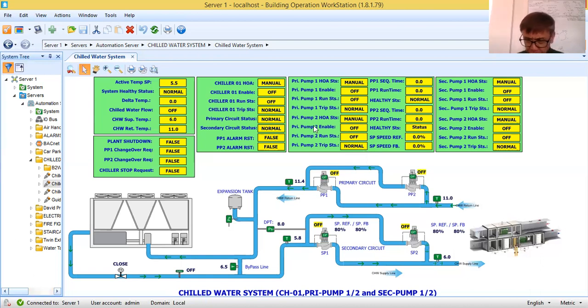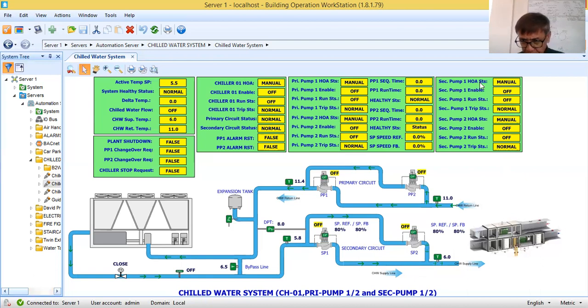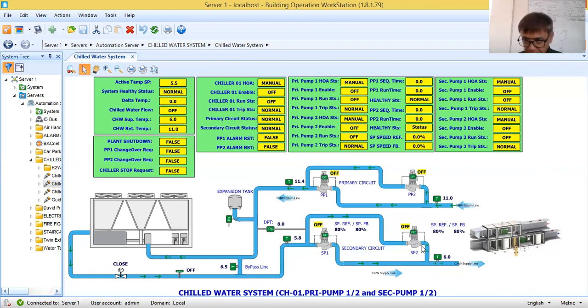The control point is the pump enable and disable command. Likewise, the other component in this chiller system is the secondary pump. The secondary pump has the same monitoring points: hand/off/auto, run, and trip. These secondary pumps are controlled by a variable frequency drive.